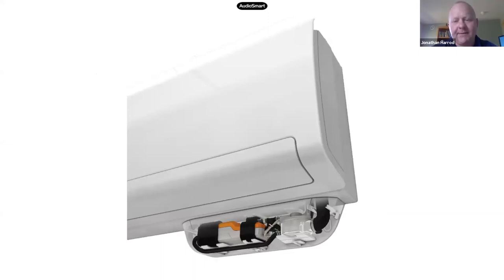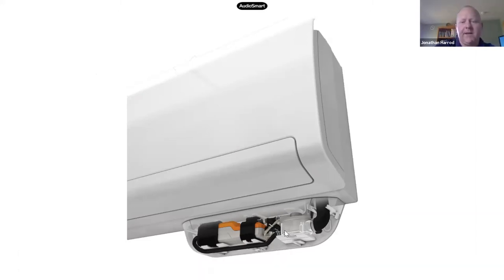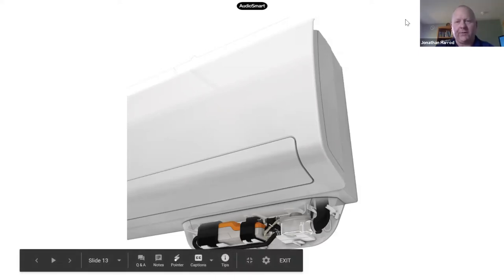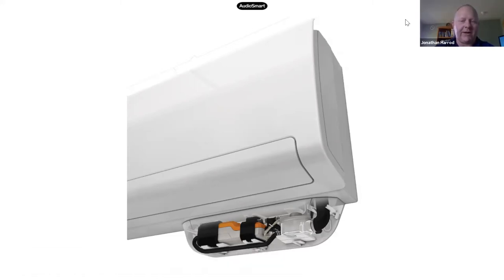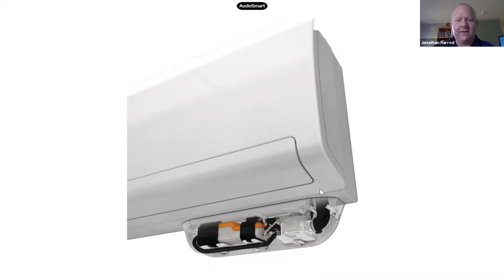If you have a situation where you can't achieve a good slope with the condensate, you can use a condensate pump. This is a little cutaway diagram showing one type of aftermarket condensate pump. So the condensate in this picture would be coming into this device that attaches onto the bottom of the unit. And in here is a little pump. It's very similar to a pump that you'd have in a fish tank or something like that. It also has a switch so that if for any reason it fails, it stops the unit from operating and making a big mess all over the interior of your house. This condensate pump can push this condensate up and into the attic and over to some easier to drain location. So this is another great solution. The one I have shown here attaches onto the bottom of the head itself. There are some that are small enough to actually fit within the head itself.